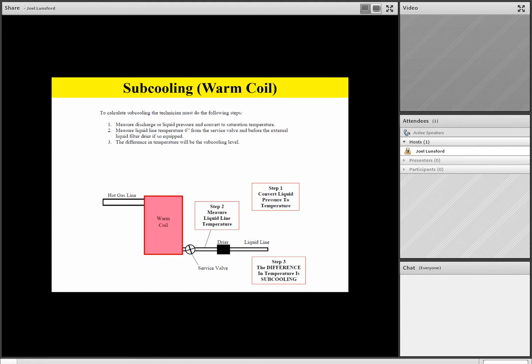So this time, let's talk about subcooling in the warm coil. Remember, team, subcooling always applies to the warm coil. It doesn't matter if the warm coil is outside. In the example, in the cooling mode of operation, the outdoor coil is the warm coil. And in the heating mode of operation, the indoor coil is the warm coil. Now remember, team, subcooling always applies to the warm coil, and subcooling will also tell us the condition of the coil. So please write this down or make a note of this.